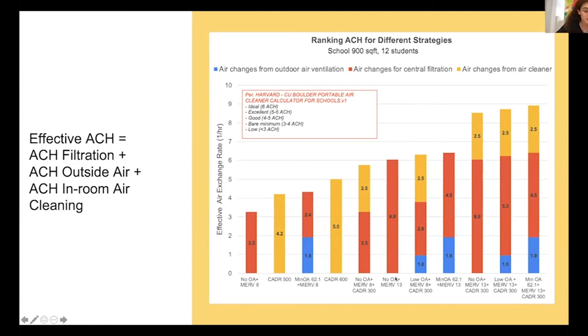So if you don't have any outside air and you have MERV 13, you can see here basically this column in red, you will have an air exchange rate of 6. By the classification of Harvard and CU Boulder, that's ideal. So imagine this, you don't need to do anything else. Even if you don't have any outside air, if you have a very good filter and you know the performance of it, you have an air exchange rate of 6. You can always do more. Like if you have, for example, the minimum outside air, the last one, per 62.1, a MERV 13 and an air cleaner, then you can have a very high air exchange rate. So this is a way for you to specify a target and say, okay, what basic technologies do I have, what is the air exchange rate?